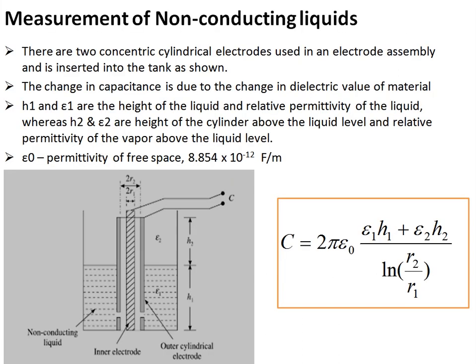For non-conducting liquids, two concentric cylindrical electrodes are used. Here, 2r₂ is the inner diameter of the outer cylinder and 2r₁ is the outer diameter of the inner cylinder. h₁ and ε₁ are the height and relative permittivity of the liquid, while h₂ and ε₂ are the height and relative permittivity of the vapor or air above the liquid level. As the liquid level rises, h₁ increases.